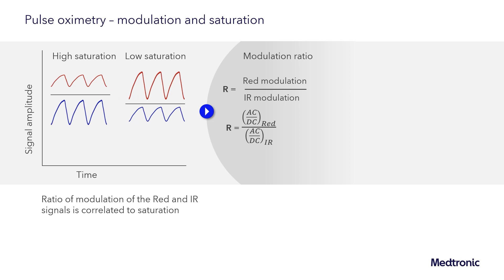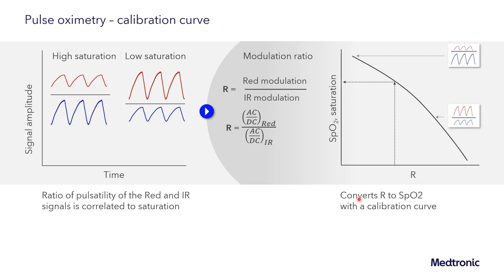That brings us to the last factor: a calibration curve can be used to calculate SpO2. The modulation ratio — the AC/DC of red divided by the AC/DC of infrared, or red percent modulation over infrared percent modulation — trends with saturation. At high saturations it is a small number, and at low saturations it is a large number. A calibration curve takes a specific modulation ratio R and converts it to a saturation or SpO2, and is typically empirically derived for that pulse oximetry setup.